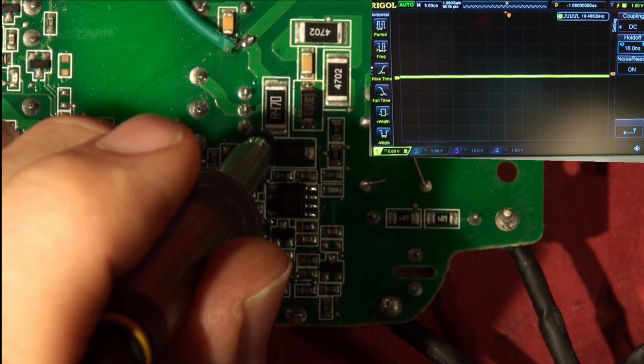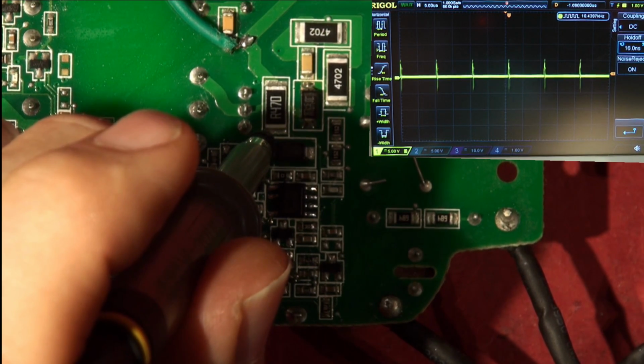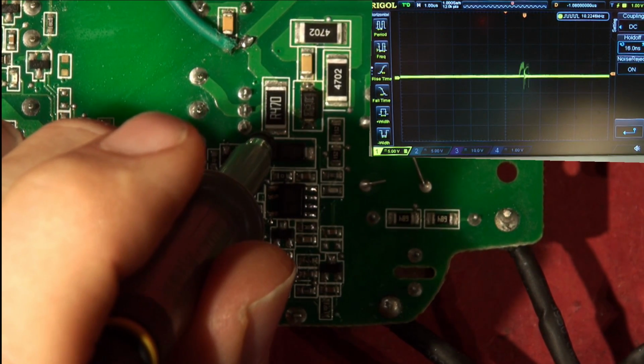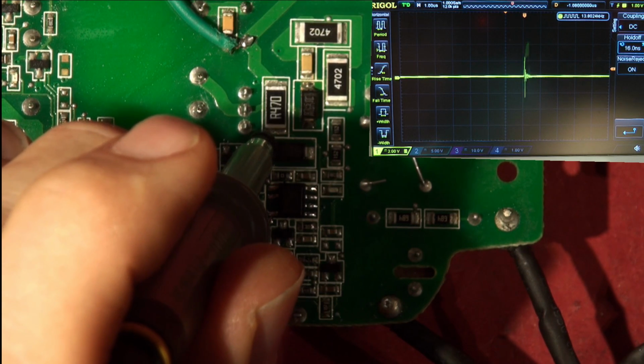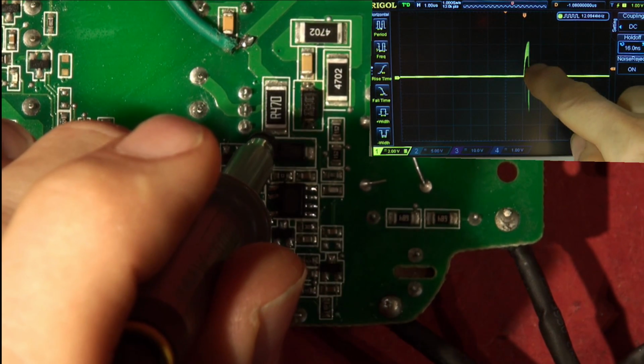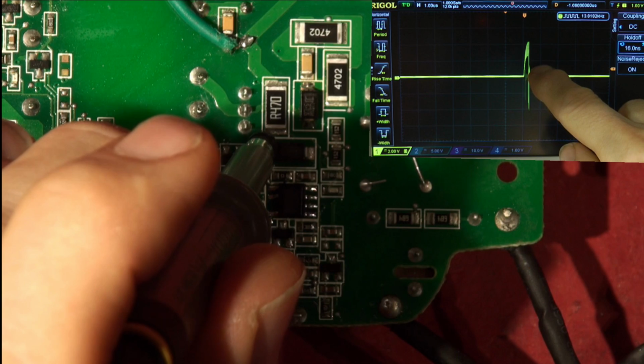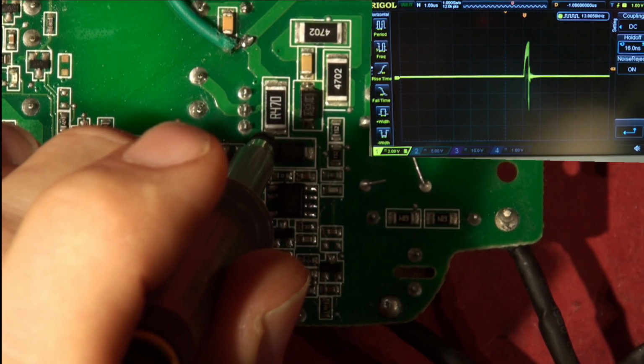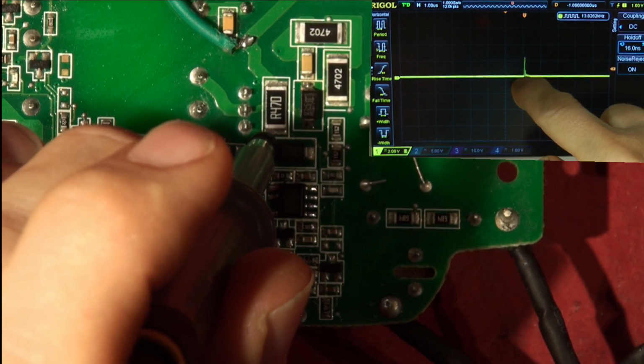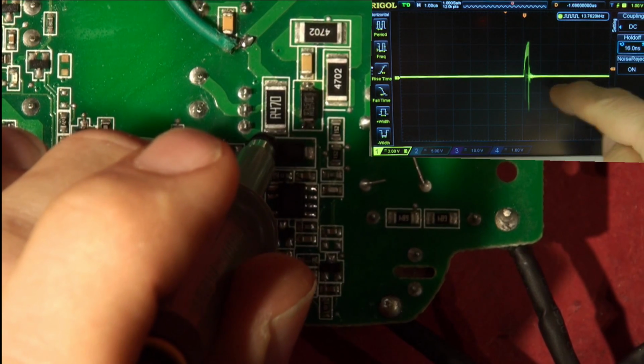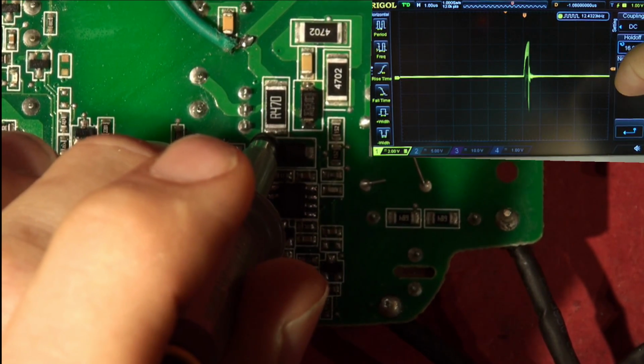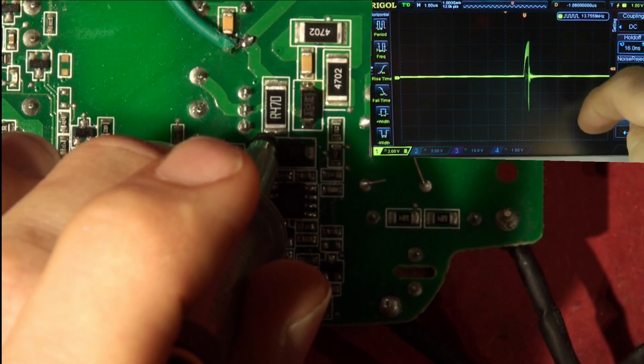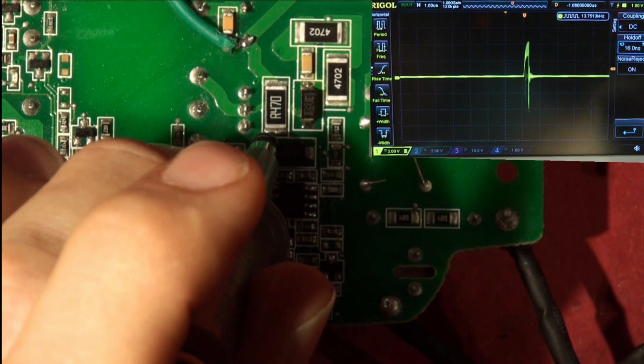And if we speed that up, put it on normal, speed it up, and have a look, turn the gain up to 2 volts. We've got 2 volts, so way over current. This positive rising pulse should be less than 1 volt, otherwise this unit will shut down the power. So it's trying to start up, but there's too much current in the primary.